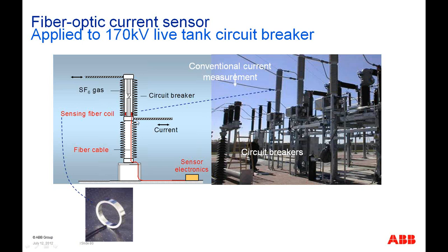It's sitting just around this pole of the breaker. So normal current flow is going to come through here, through this lower level, then through the breaker, through the contact, then out again. And we can put this rotator, or this optical current transformer, right around the breaker itself. And you can see a picture of that would be this. It's sitting right over here. It would be sitting right in here.